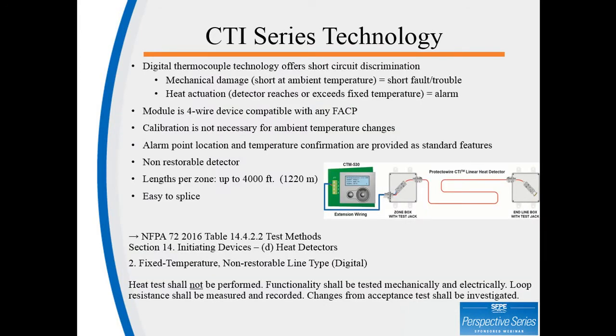Digital thermocouple technology offers short circuit discrimination. Mechanical damage, a short at ambient temperature, creates a short fault or a trouble condition, not an alarm. Heat actuation, when the detector reaches or exceeds its fixed temperature, will render an alarm. The module is a 4-wire device. It's compatible with any fire alarm control panel. Calibration is not necessary for ambient temperature changes.